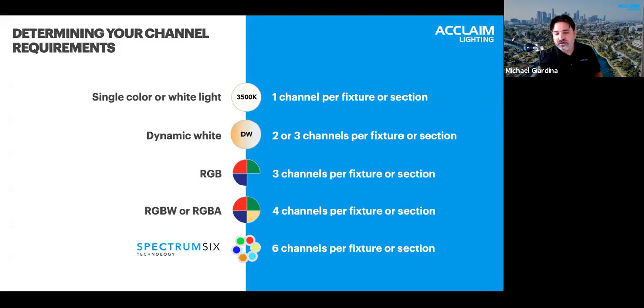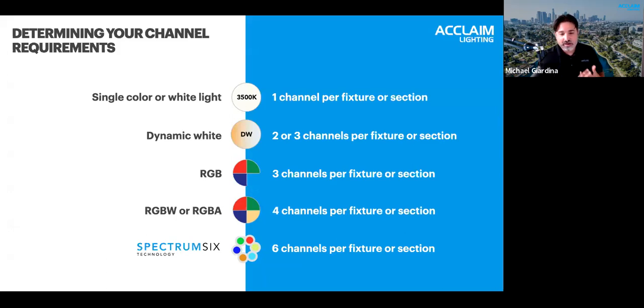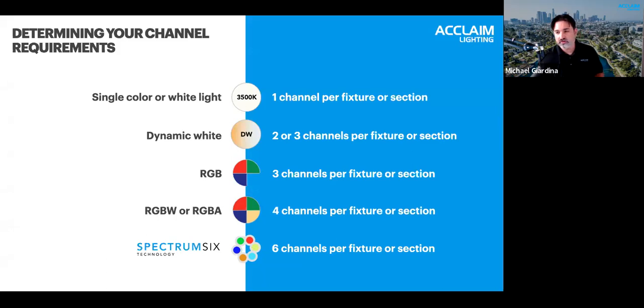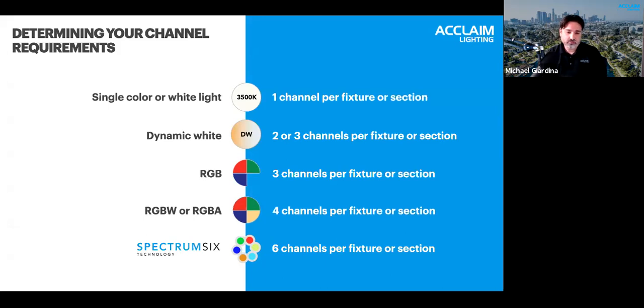Looking overall at these options, when reviewing a specification we can count up the channels based on the type of fixture to determine how many individual channels are required for the desired control. Some fixtures may have additional channels for things like a dedicated dimmer or a zoom. Most Acclaim fixtures don't have these, but if you encounter other manufacturers' fixtures they may, so take that into consideration.